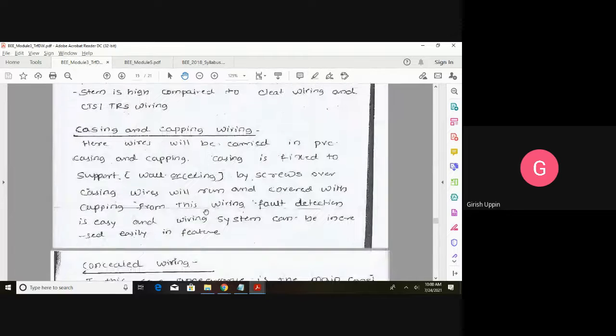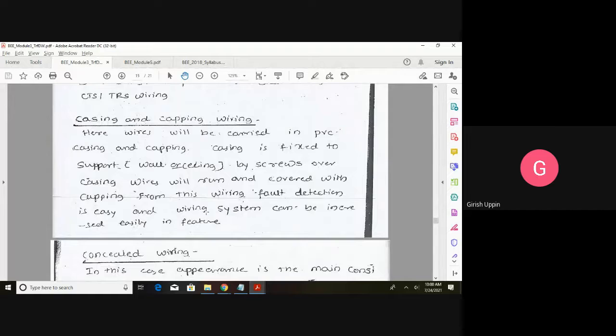Casing and capping wiring is the one you have in your classrooms, which we can open. The casing is fixed onto the wall, the wire runs inside it, and on top of that the cap is put. The advantage of this type of wiring is that if there is any need, you can immediately open the cap, put additional wire and additional points without any problem. In other types of wiring, it is very difficult. It is also very easy to locate faults, because we can open the caps and check where the fault has occurred.